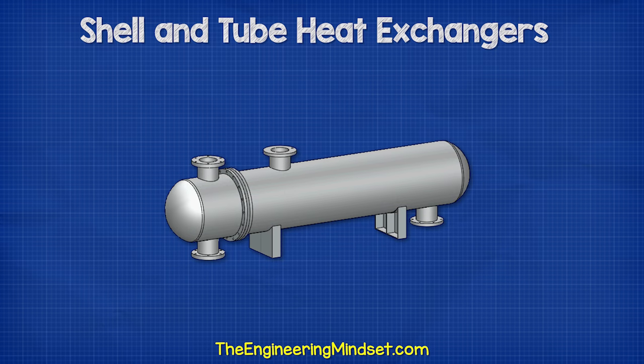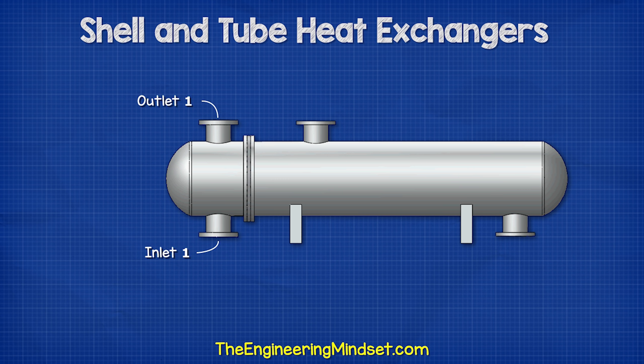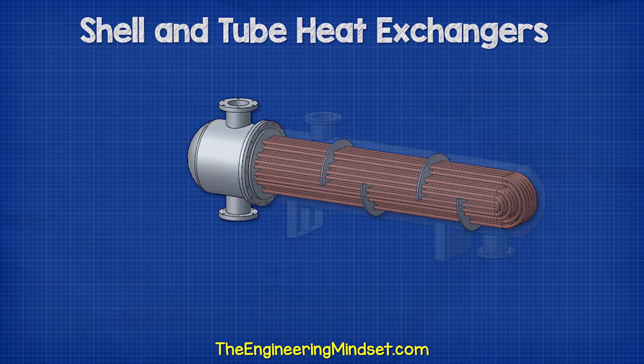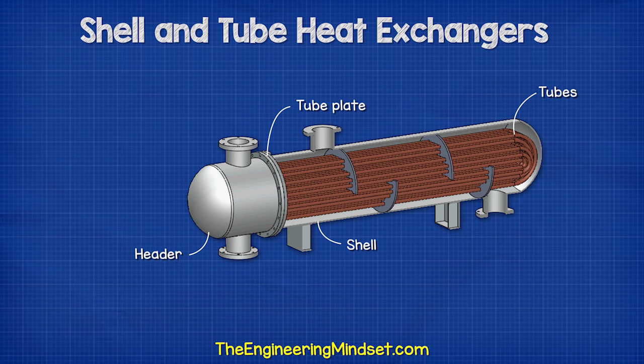Shell and tube heat exchangers will look something like this. With this design we normally find the inlet and the outlet for one fluid at the very end of the heat exchanger, known as the header. Then we have another inlet and outlet for fluid 2 on the main body, known as the shell. Inside the unit we have the tubes, which bend and loop around to start and finish at the tube plate, which sits between the shell and the header.